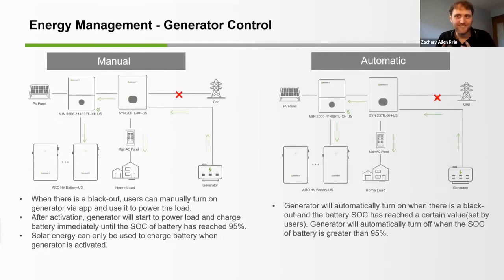Okay, so kind of putting everything together, this is how the system is laid out with the SYN device. Remember, this is a V3 model inverter, and the SYN will connect to the main panel. It has a breaker for the main panel, but it also has the breaker for the grid and a separate generator input. So when there is a blackout scenario, the customers could do two options. If they have a generator that supports 2-wire start stop, that is the most ideal, right? So the generator is automatically turned on by the SYN device.